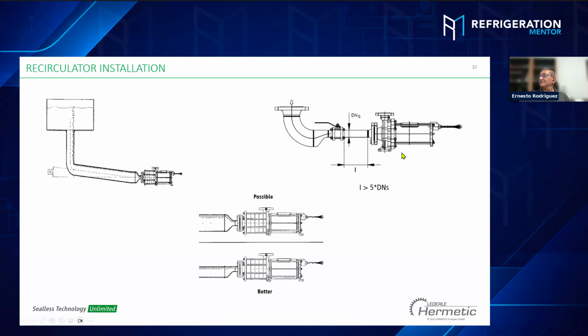Okay, great. For example, this will be a minimum of 5 times the diameter of the pipe. For example, this pipe is 2 inches, so the distance needs to be 10 inches minimum. And what can happen if you're not? That'll cause cavitation, maybe. Well, we have turbulence right here. We don't need any turbulence on the suction of the pump. It can be cavitation, it can be flash gas, anything. Any type of turbulence can cause problems with the pump. And the same way with the suction, this is the eccentric and concentric. This is the best way to install it.